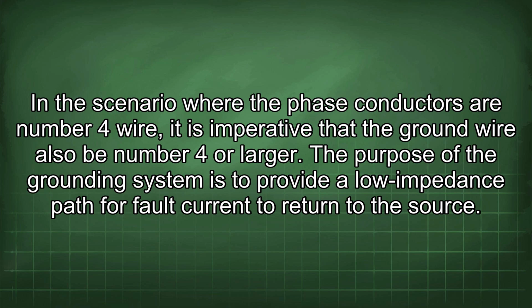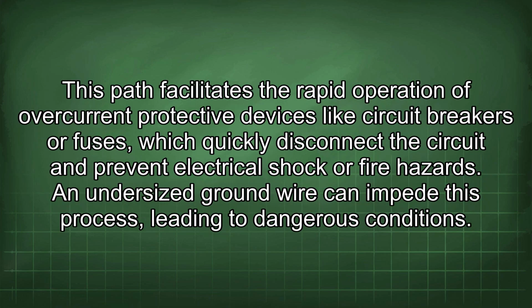The purpose of the grounding system is to provide a low impedance path for fault current to return to the source. This path facilitates the rapid operation of overcurrent protective devices like circuit breakers or fuses, which quickly disconnect the circuit and prevent electrical shock or fire hazards. An undersized ground wire can impede this process, leading to dangerous conditions.